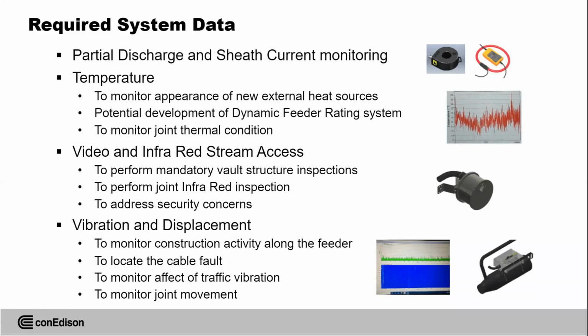The next sensor is sheath current monitoring. Why is it important? For a transmission system, we want the maximum rating for the cable. So maximum rating means no heat sources anywhere around. So you don't want to have circulating current in your sheath or in the shielding of your cable. Because if you do, this is a heat source right on top of your cable. That can reduce the ampacity of that conductor size by 10-15%.